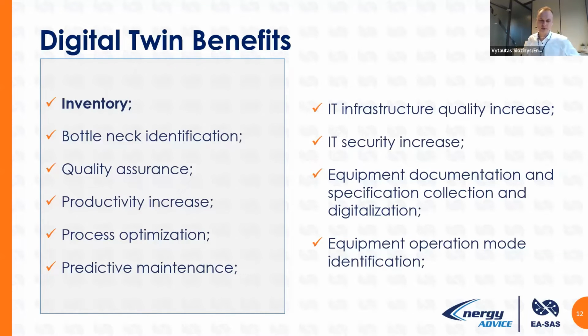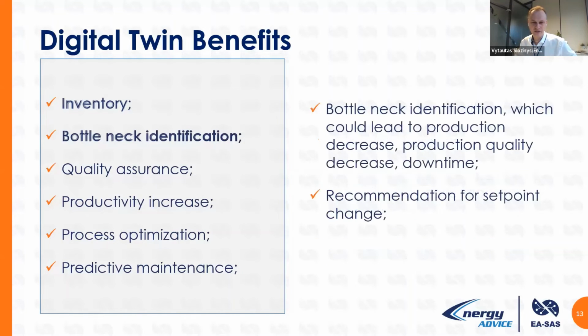And equipment operation mode identification. So if we have a pump, we should understand how it behaves. So it's the operation mode, how it behaves. If we have a fan, is it the right set point, the right mode? If it is a refrigerator, a chiller, a furnace, whatever, right operation modes are very important. Bottleneck identification, because bottlenecks could lead to production decrease, quality decrease and downtime. So, recommendation for set points change: the digital twin, in fact, through recommendation of optimum set points, reduces downtime, increases production quality, etc.